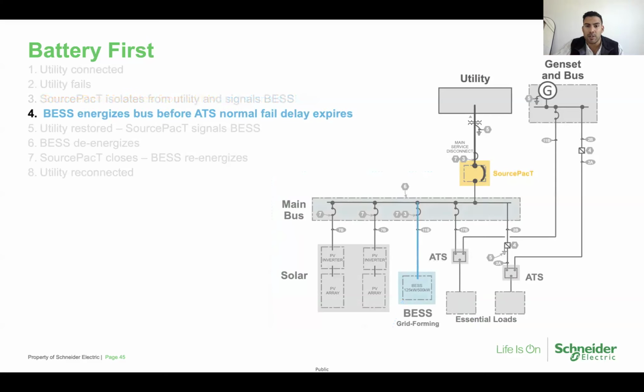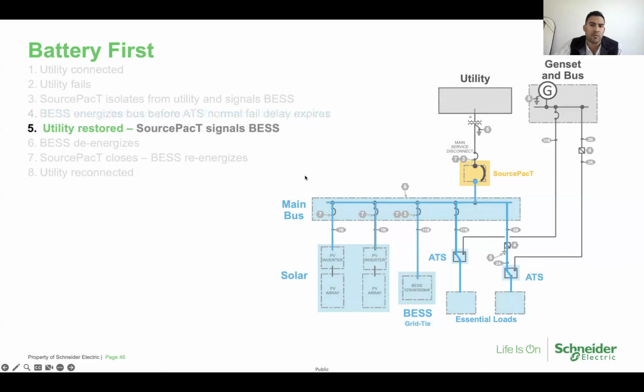That energy storage system will come online very fast, as the inverters operate quickly. Now your main bus is energized from battery power, and your inverter system is able to come online. Those ATSs, again, it's happening instantaneously, stayed on source 1, and there are inhibit transfer contacts within the transfer switch to inhibit transfer to source 2. So they're still connected to source 1, and you'll remain connected to source 1 and the battery energy storage system until the utility has been restored.